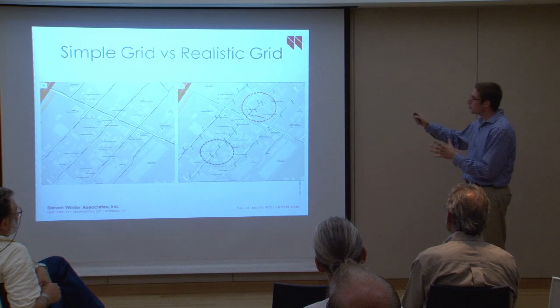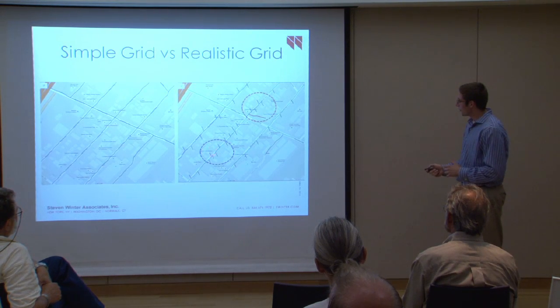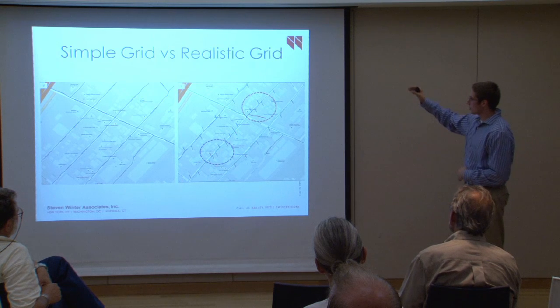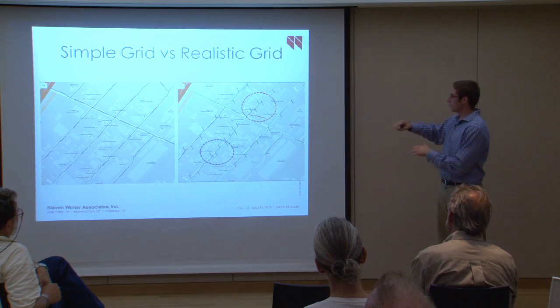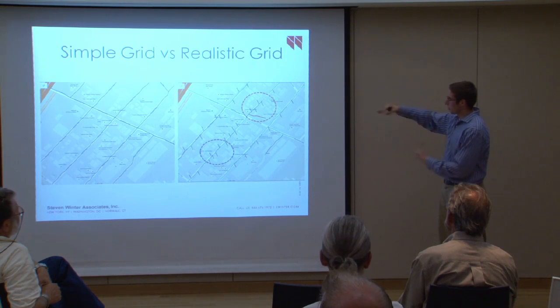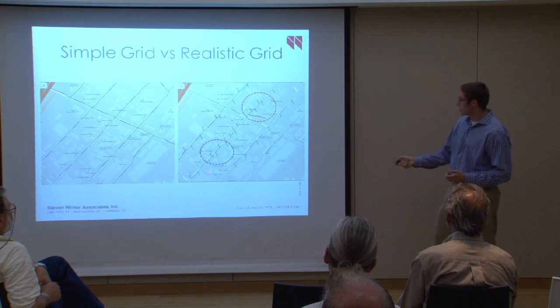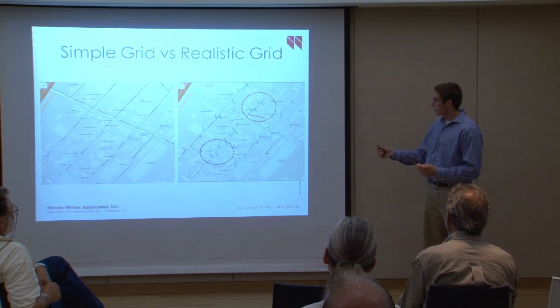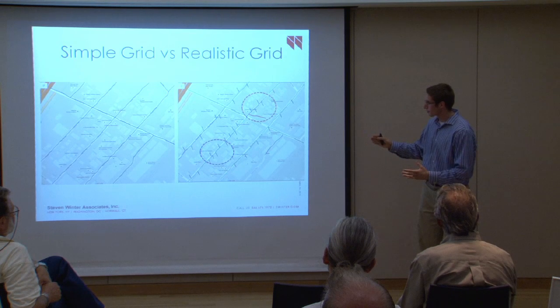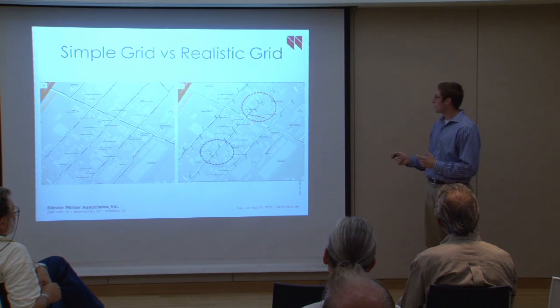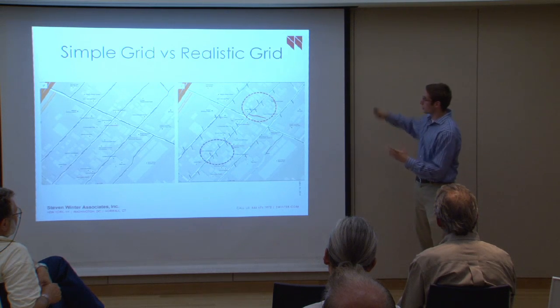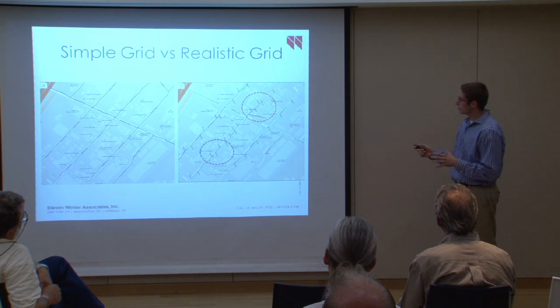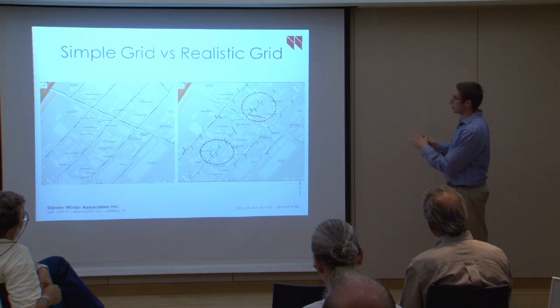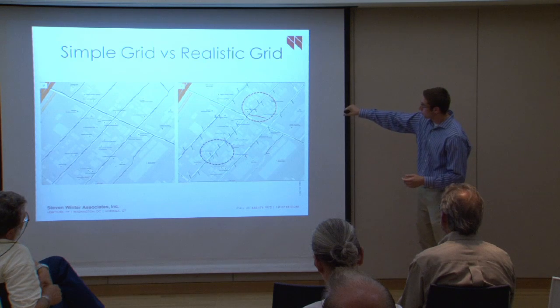I've included two examples you might encounter. This is an example where you have a primary voltage line running down the road and there's a transformer in each building dropping it down to usable voltage. One option is you could put a switch on each end of the line to isolate your grid. Another example is you come to a secondary voltage line at the end of the feeder - you could put a switch there and isolate your grid. This is probably a preferable situation because it doesn't interrupt any other parts of the grid if you just switch off this section.